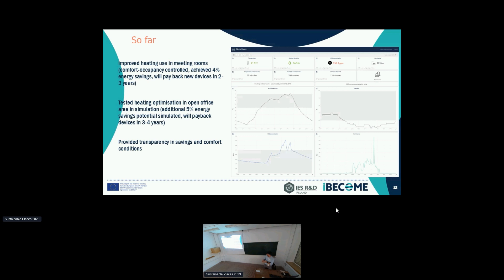Using our physics-based model, we calculate energy savings and prepare what-if scenarios for the building's decarbonization. So far, this winter we achieved 4% energy savings in meeting rooms, which will pay back the new devices within 2-3 years, and comfort was hugely improved. This morning's presentation showed that in an open office area we can achieve an additional 5% energy savings with a 3 to 4 year payback. We also provide full transparency to everyone in the building on energy savings and comfort conditions.